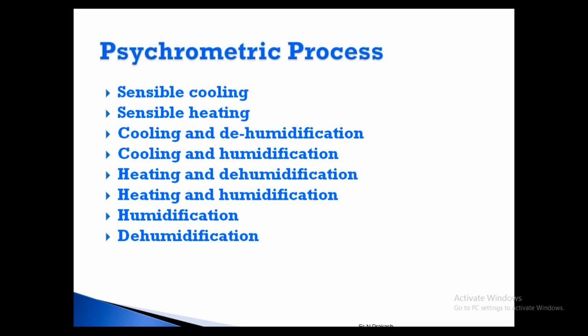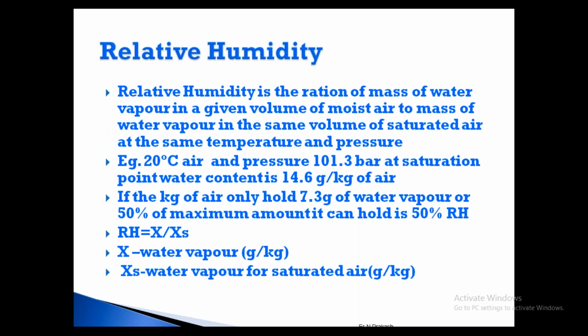It is the mass of the moisture, the water vapor, in the air. It is a comparison. For example, in 20-degree air, the water content when fully saturated will be 14.6 grams per kg. That is where dry bulb and wet bulb will both be the same. That means saturated condition. When you see in your hygrometer that dry bulb and wet bulb are the same, that means fully saturated condition. Maximum, 100% RH it is holding. So for example, at 20 degrees centigrade, it is holding 14.6 grams per kg.